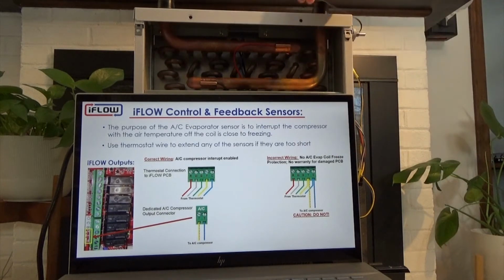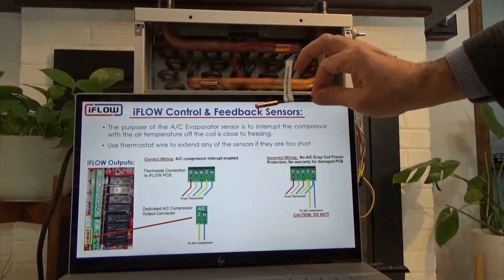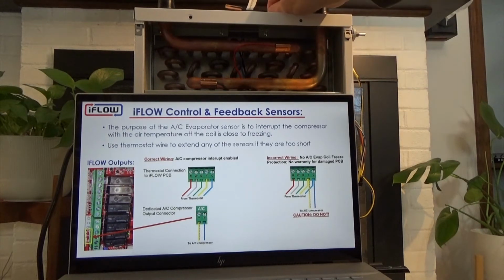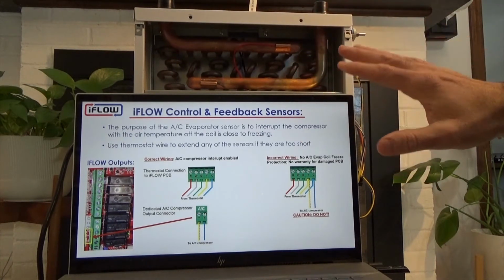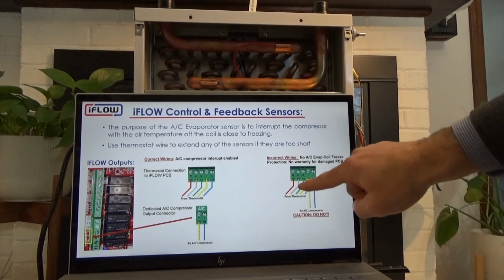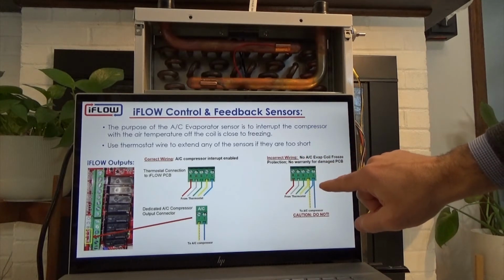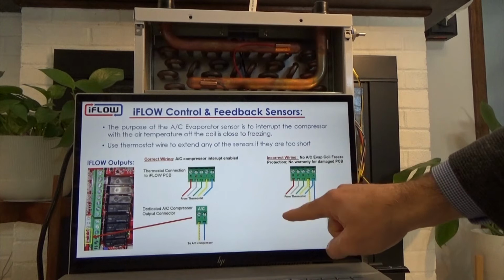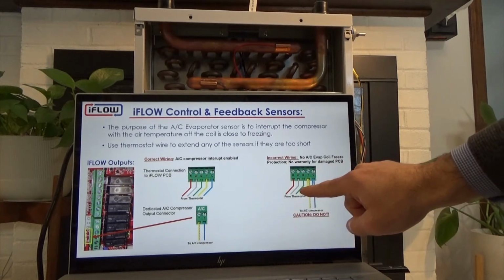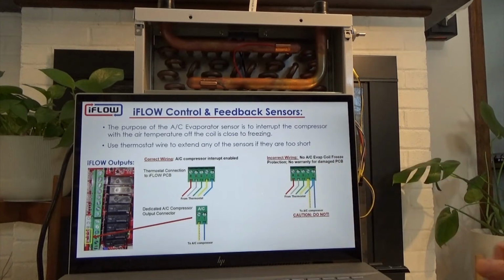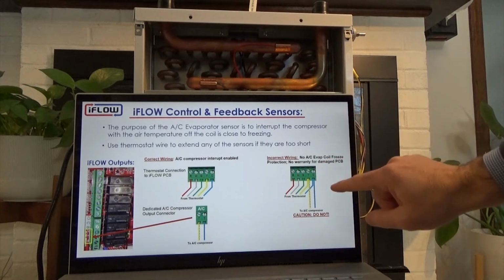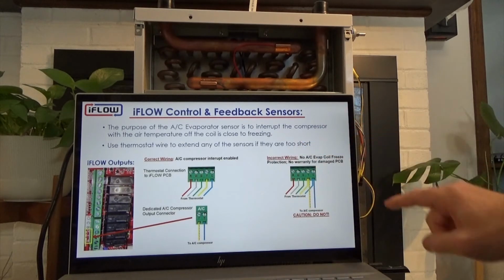When our sensor sees a temperature that is getting close to freezing, I want to turn off the compressor. If we've wired it this way, it is impossible to turn off the compressor because it's getting its signal from the thermostat. So this is incorrect, and you will not have freeze protection if you wire it this way.